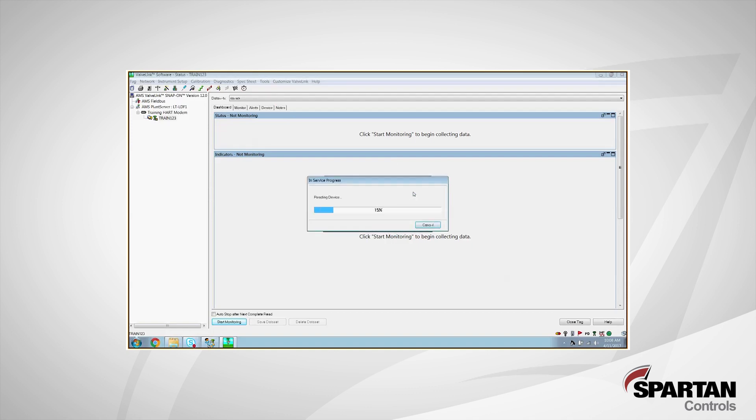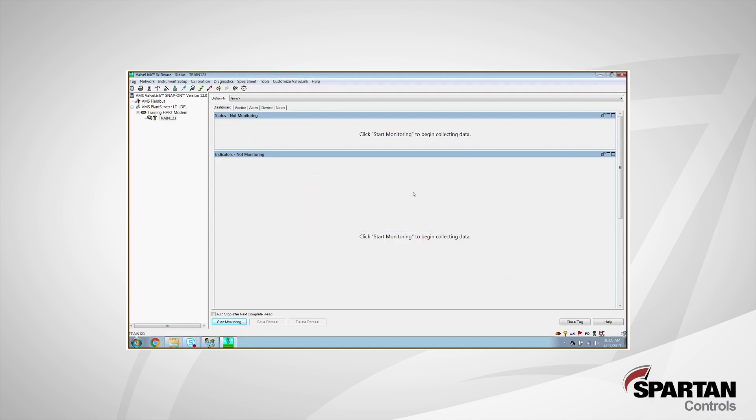It's always good practice now at this point to physically stroke your valve just to make sure that we're going to be hitting our set points and that everything's matching up. So we always recommend doing a zero, 25, 50, 75 and 100% steps just to make sure everything lines up and that it's fully functioning. And it looks good on my end.